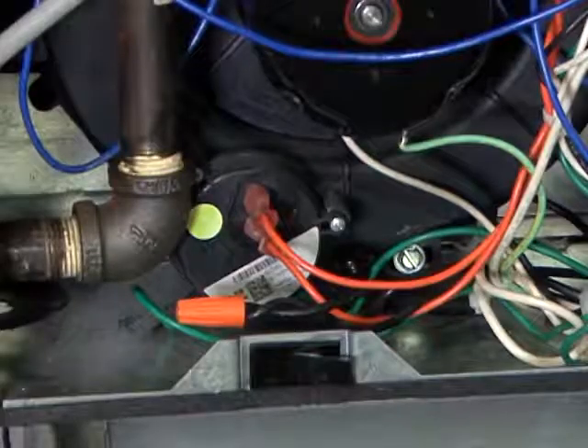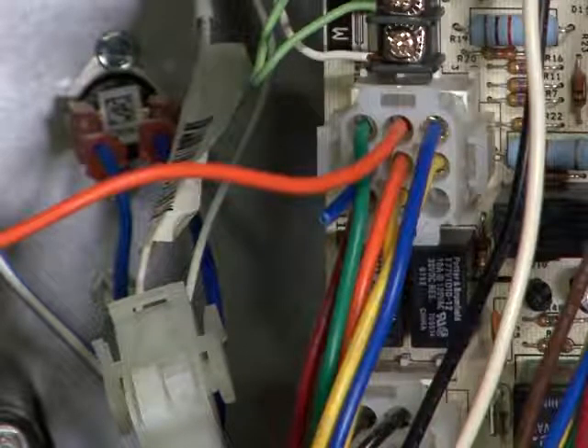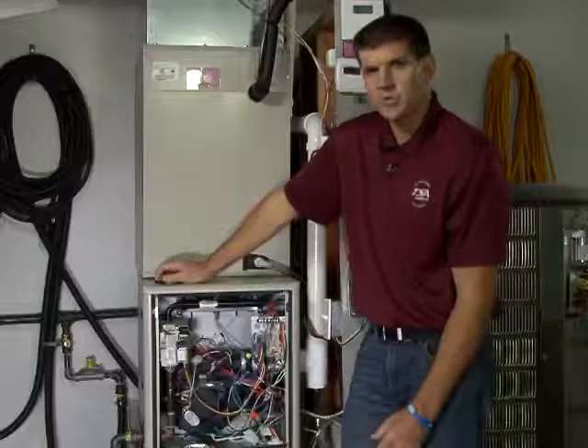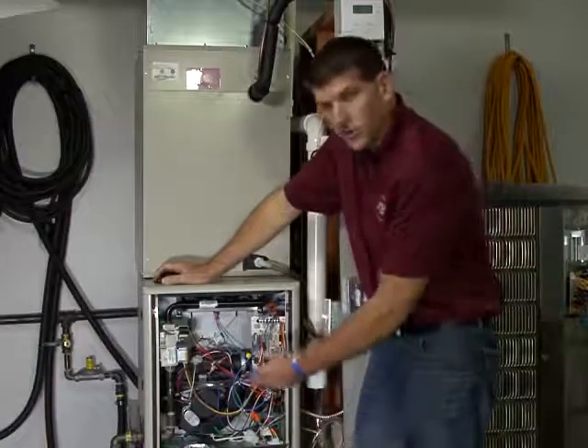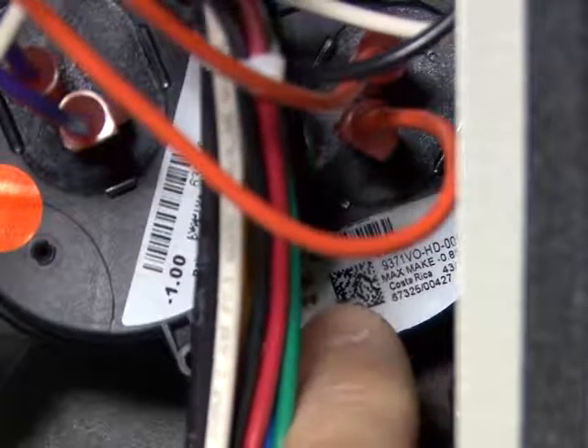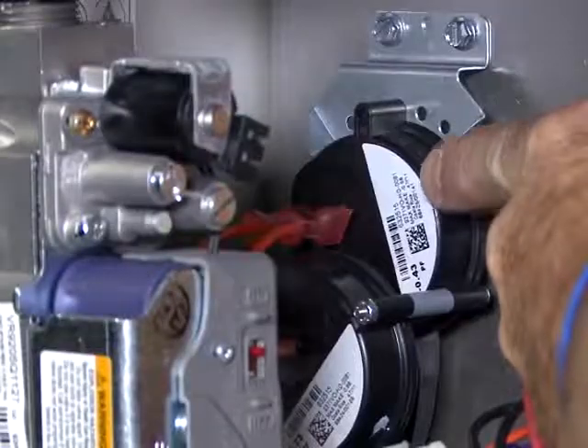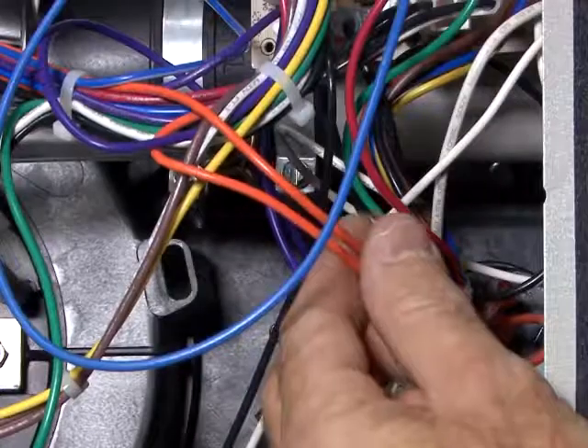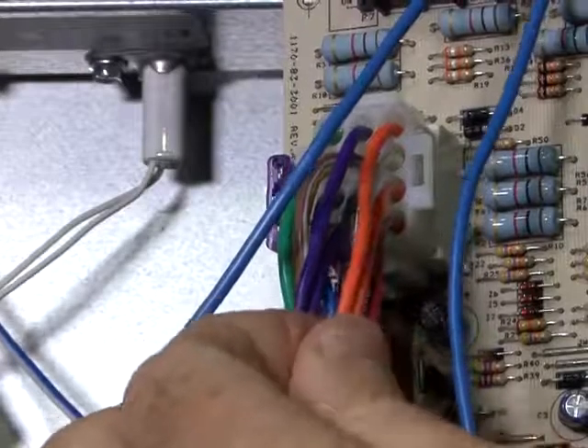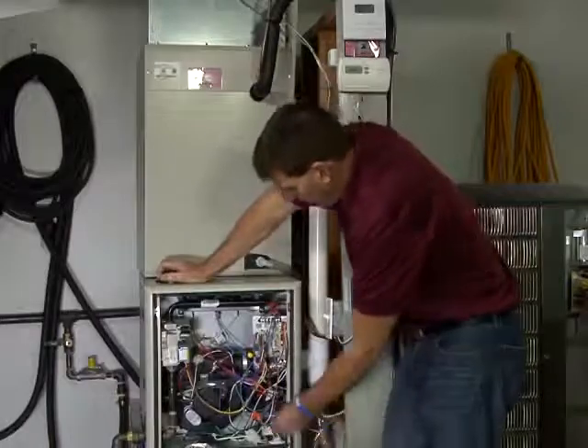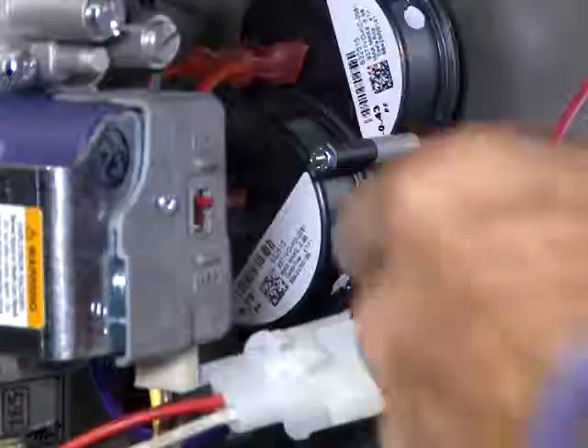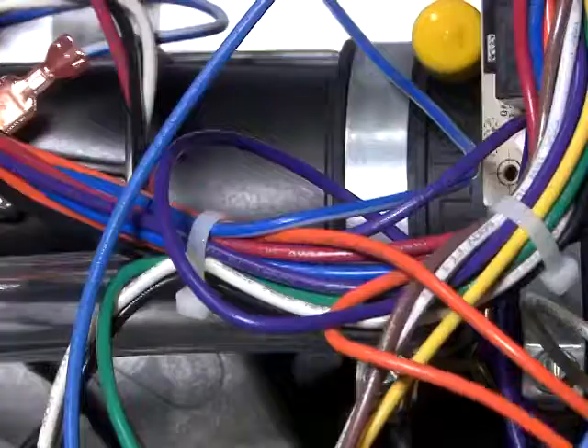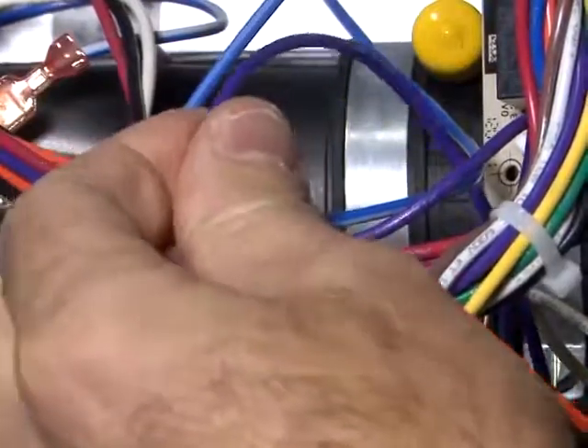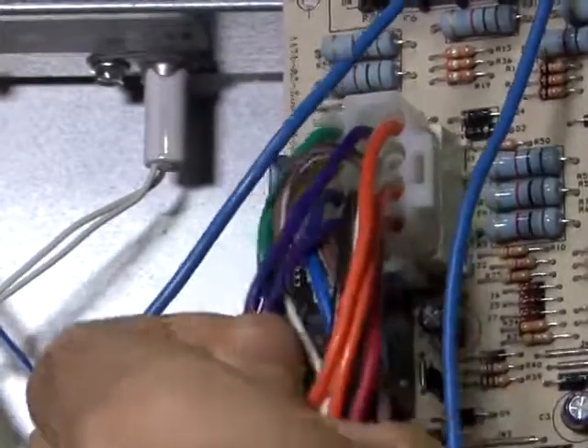Our 92% and 95% single stage gas furnaces have two pressure switches. We have a condensate pressure switch and a vent pressure switch wired in series on the two orange wires that go back and connect to the 9-pin Molex plug to the control board. A two-stage G7 95% gas furnace has four pressure switches. We have a low-fire condensate pressure switch and a low-fire vent pressure switch. These two pressure switches are wired in series on the two orange wires that go back and connect to the 12-pin plug at the interface control board. We also have a high-fire condensate pressure switch. We have a high-fire vent pressure switch. These two pressure switches are wired in series on the violet wire that goes back to the 12-pin Molex plug that connects to the interface control board.